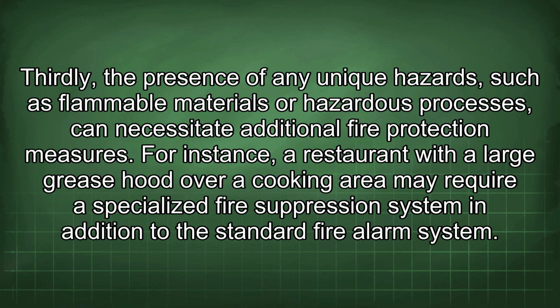Thirdly, the presence of any unique hazards, such as flammable materials or hazardous processes, can necessitate additional fire protection measures. For instance, a restaurant with a large grease hood over a cooking area may require a specialized fire suppression system in addition to the standard fire alarm system.